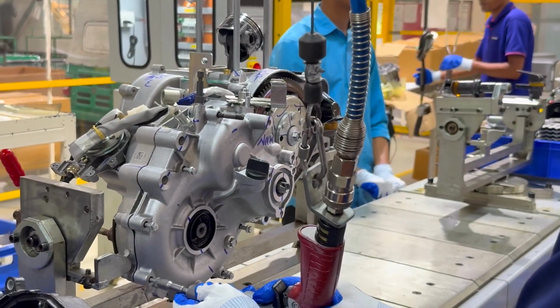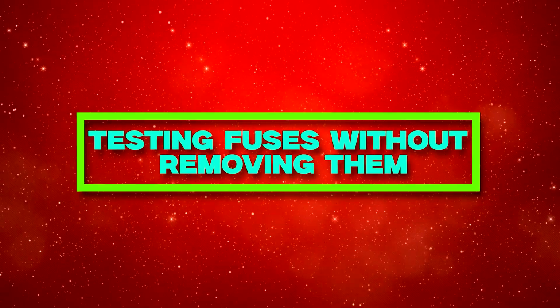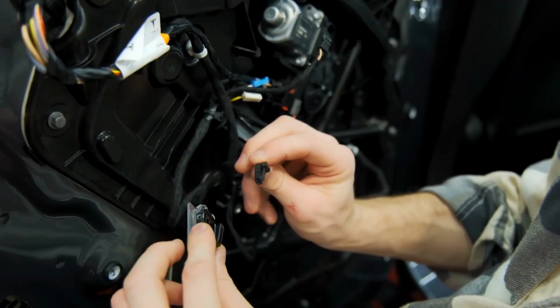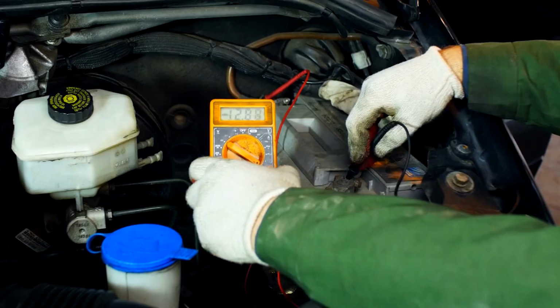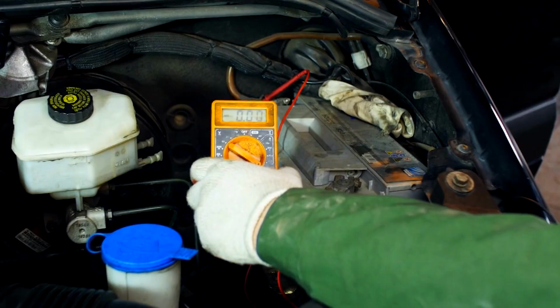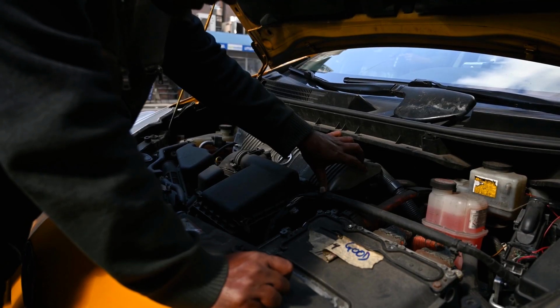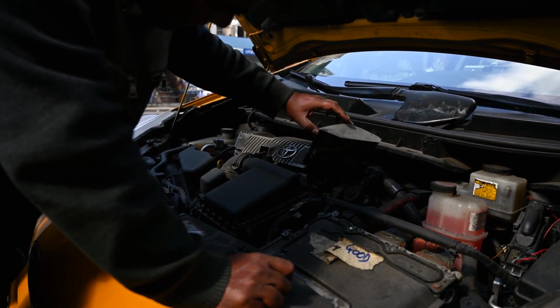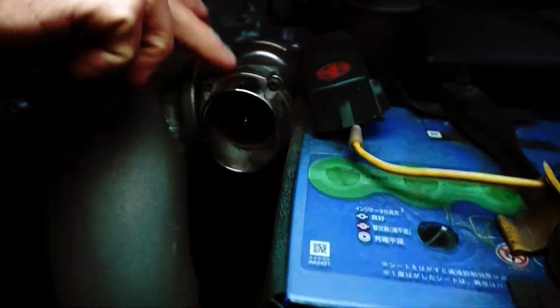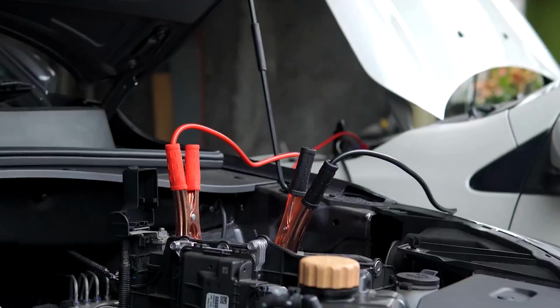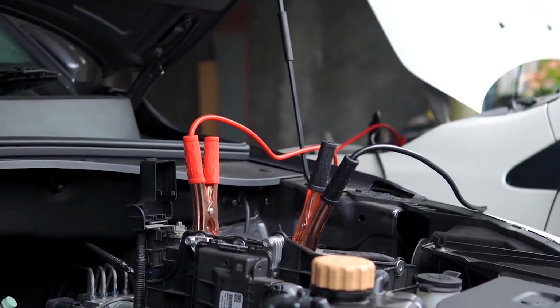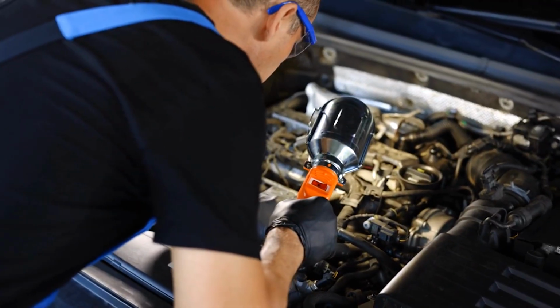Testing fuses without removing them: visual inspection is how most people test fuses, pulling them out one by one and looking for a broken metal strip, and that approach misses problems constantly. A fuse can look completely intact with nothing visibly wrong and still fail to deliver power because it's making poor contact, and you'd never know it from looking.